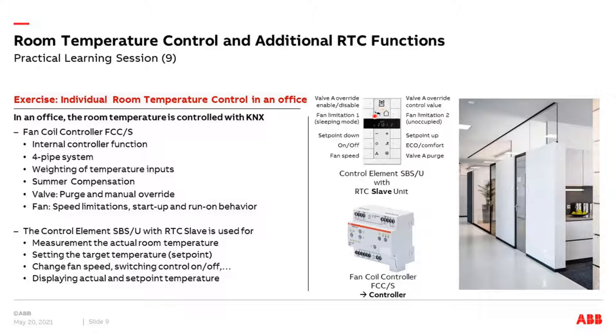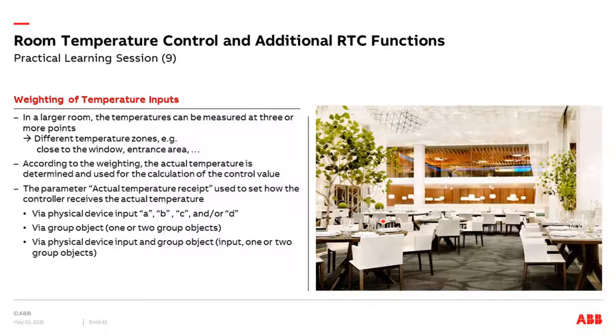We have built inside the room a fan coil unit which works in a four-pipe system, and we want to do these different additional functions: weighting of the room temperature, summer compensation, the valve purge, and the limitations. Regarding weighting of the temperature input — for example, we have different zones in an open-plan office or in a room. We can measure the temperature at different points and then weight this temperature for calculation of the set point. On the fan coil controller we can use the temperature which comes from the room temperature sensor via KNX, and also temperatures connected to the inputs of the device, then use the parameters for weighting.